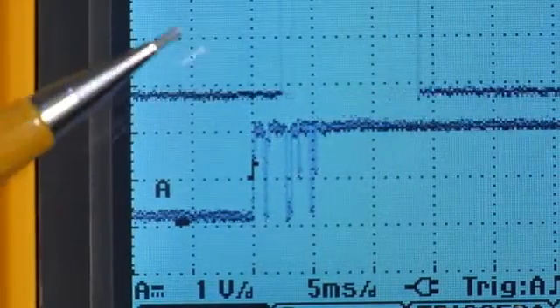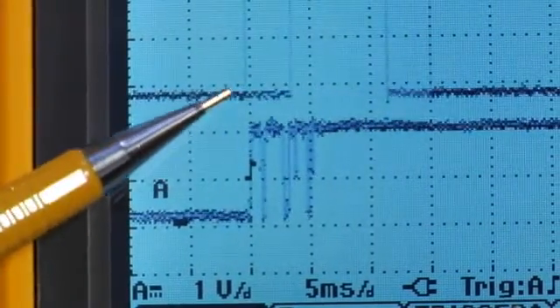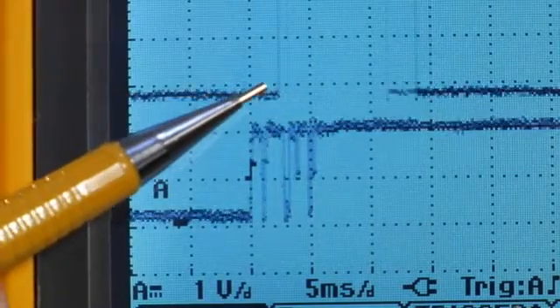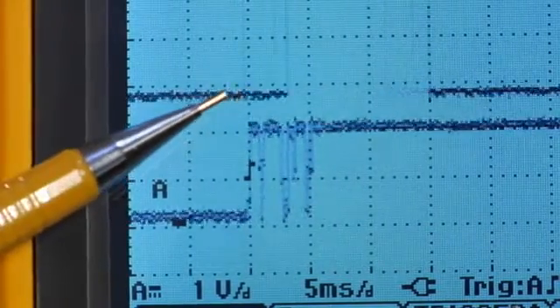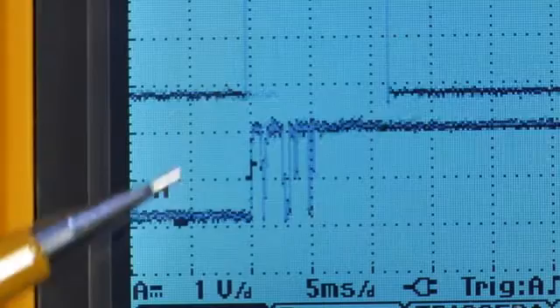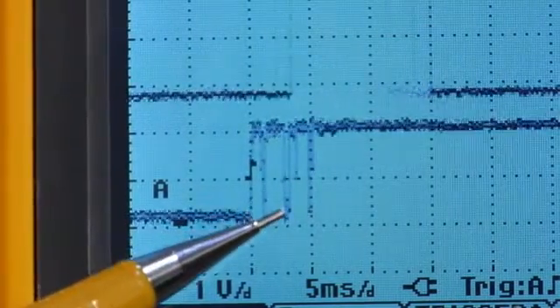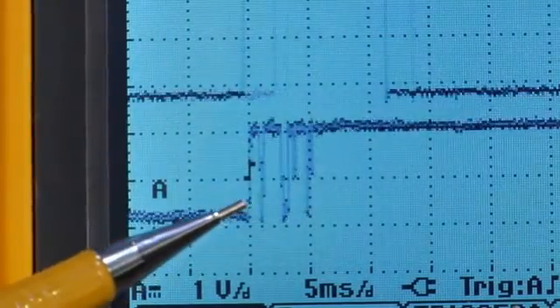Zooming in to look at it in even greater detail, you can see the output from the proximity switch isn't changing state from off to on in one single transition. The contacts are bouncing on and off about 5 milliseconds before the output stays on.